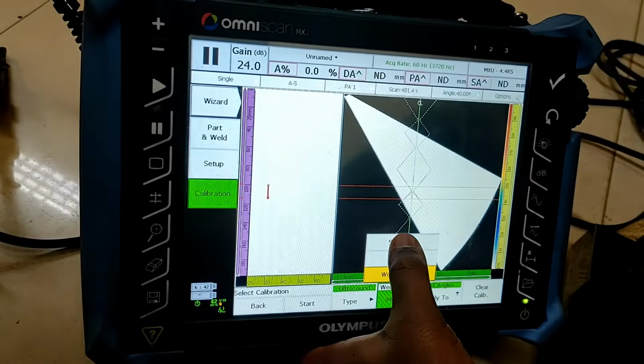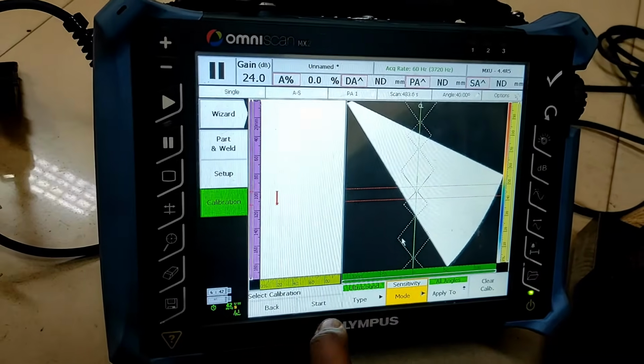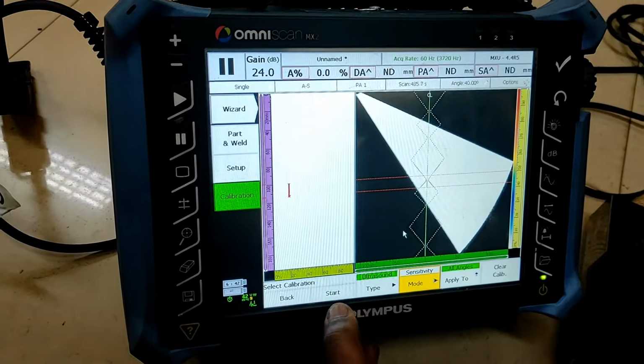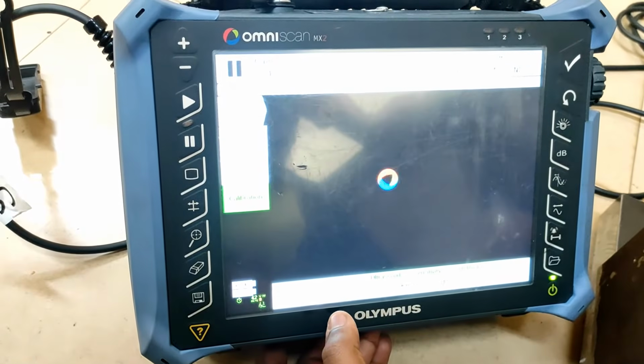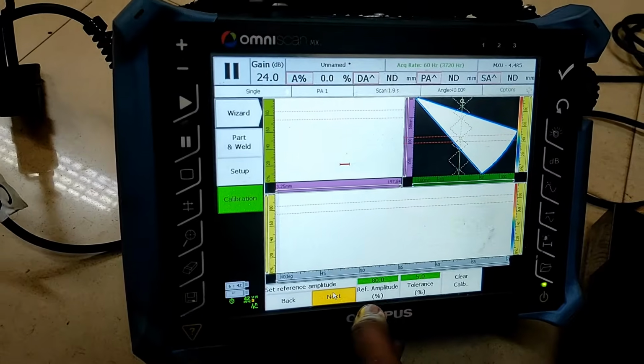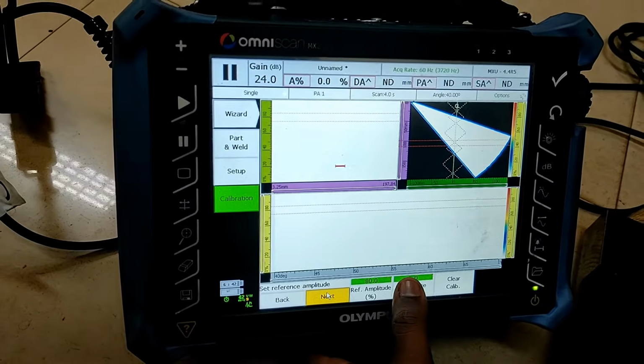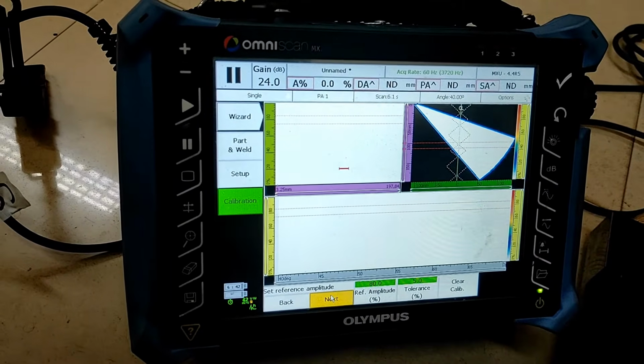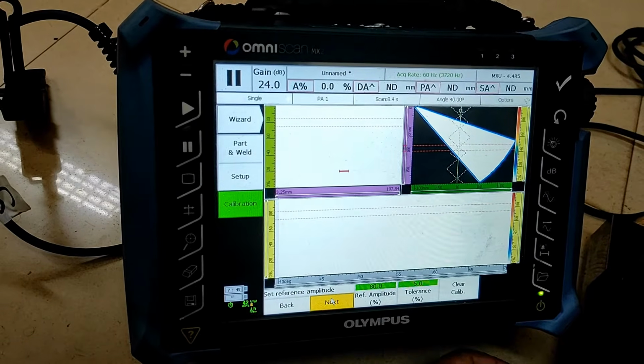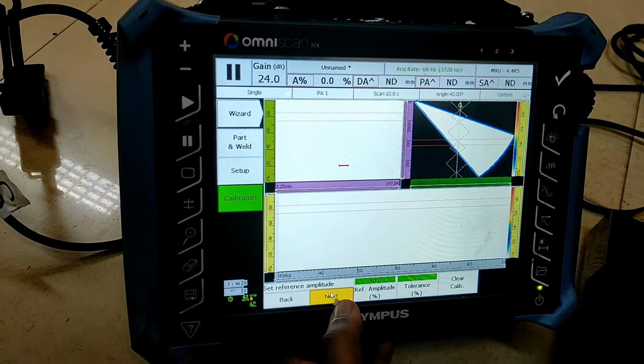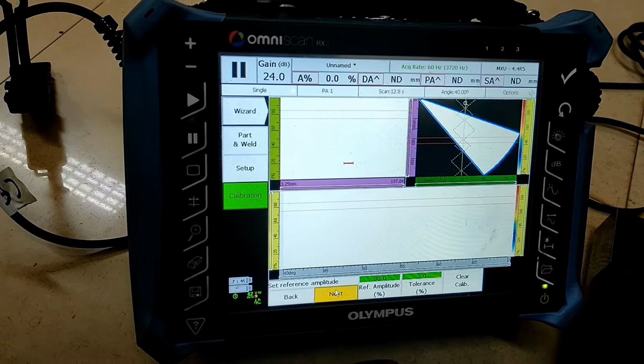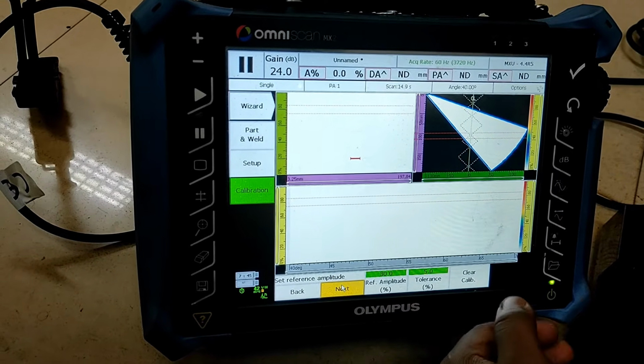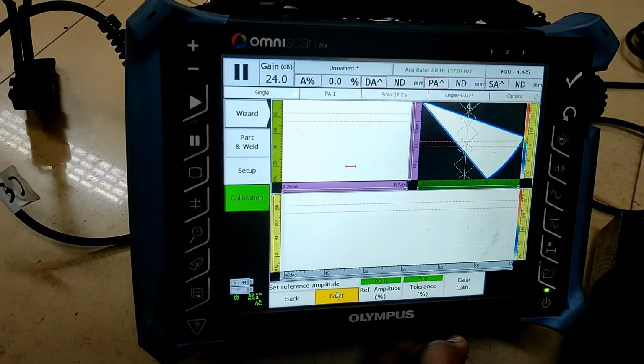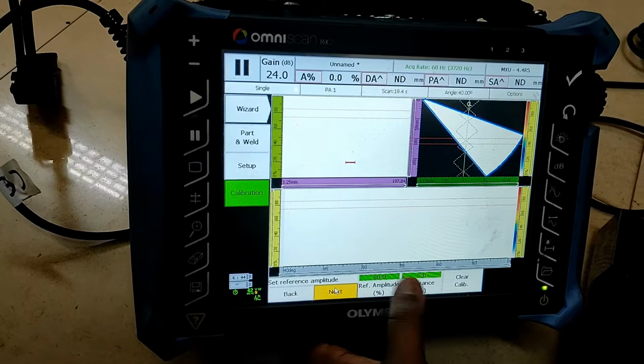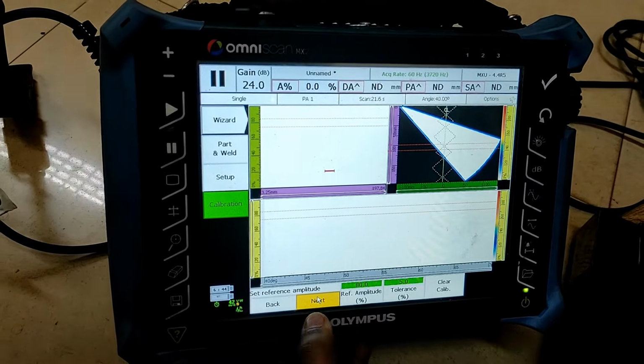Before that, we have to do the sensitivity for calibration setting. Just go here for sensitivity and press start. Now the reference amplitude should be 80 because in the sensitivity for all angles we are going to make 80%. All the angles should be in 80%. Some angle will get higher amplitude, some angle lower amplitude. So we are going to make all angles to 80%.